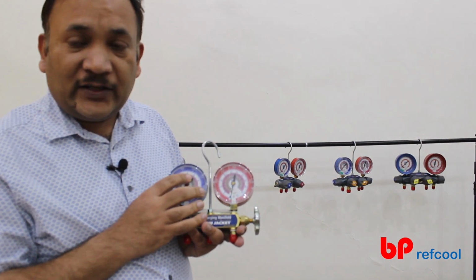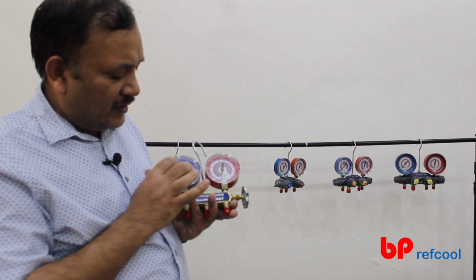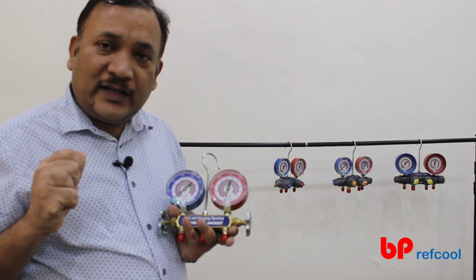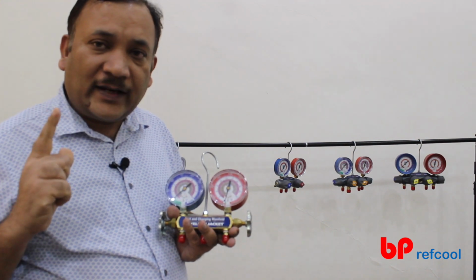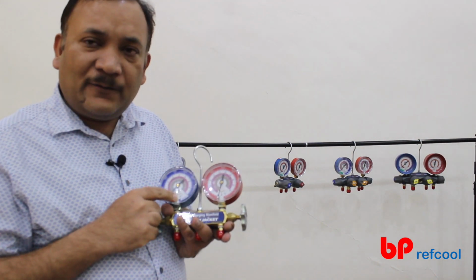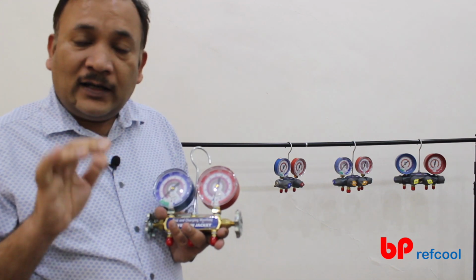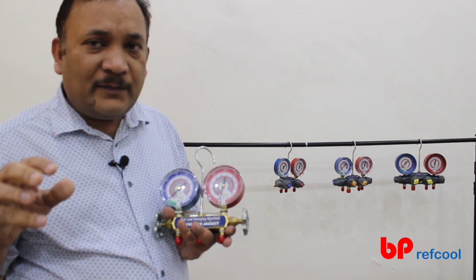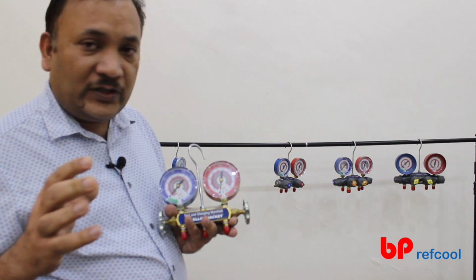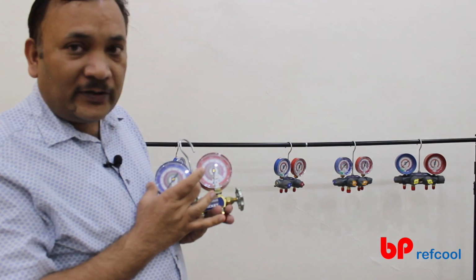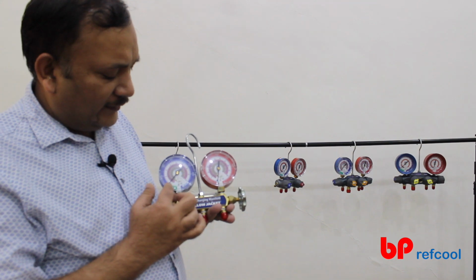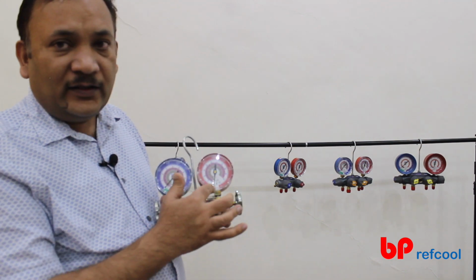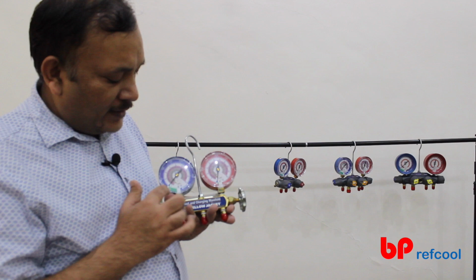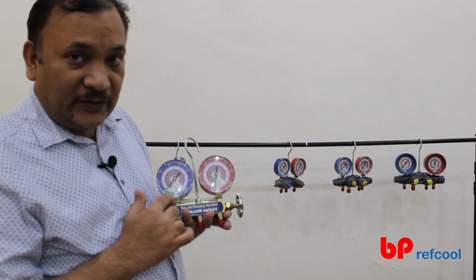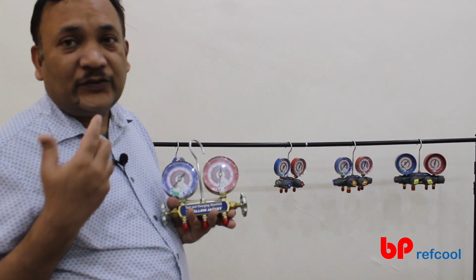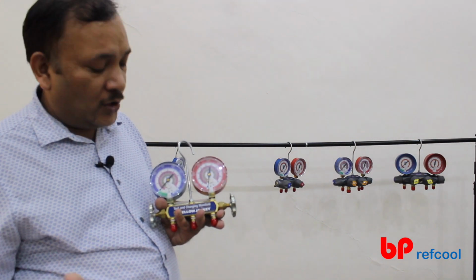Then there is the accuracy of the gauge, which can be class 1 or class 2. These gauges are class 1 gauges. Class 1 really talks about 1% accuracy, so they would have 1% accuracy of the full rating of the gauge. Another important part of a gauge: you see there is a compound gauge on the suction side, which will always have some vacuum, and a full pressure gauge on the condenser side. The color difference matters too: this green is for vacuum. It is just to give you an indication whether the system is under vacuum or not.